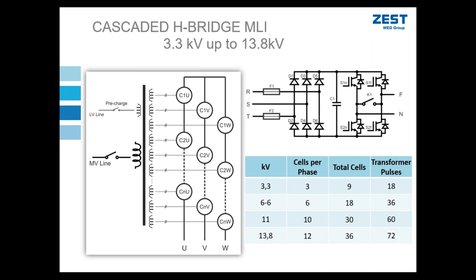The next topic, now that is finished, we're going to look at the cascaded H-bridge multi-level inverter topology. This topology is a lot more flexible in terms of its output voltage capability, because we can string together as many series power arms containing IGBTs as we want. We put them in series and we can add as many as we want. This allows us to supply from 3.3 kV right up to 13.8 kV output on these drives. So you've seen this topology, I'm sure, many, many times. Let's just cover it in some detail.